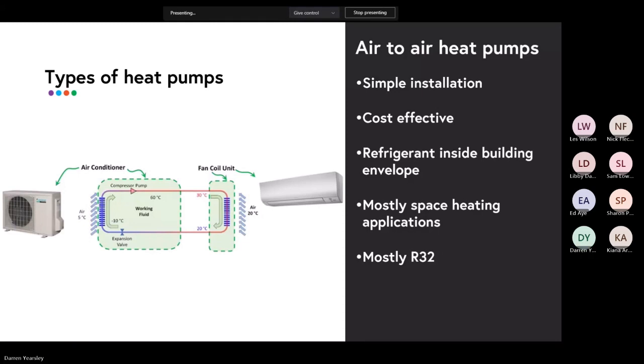So it's unclear about where this particular market's going to go, these very cheap split systems, because if R32 becomes uneconomic because of the GWP score, it's unsure about what refrigerant they'll actually move to if they're looking at bringing the refrigerant inside the building envelope.